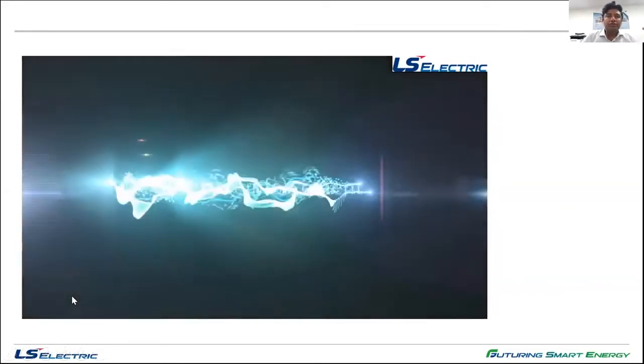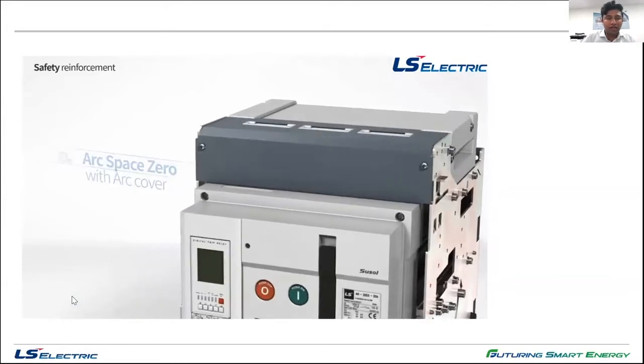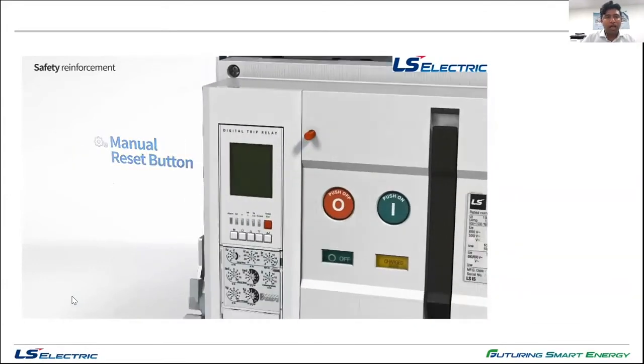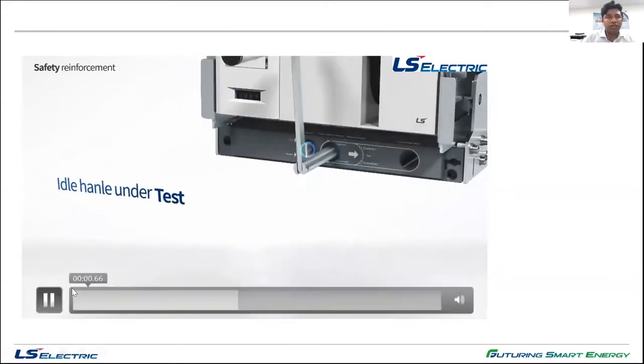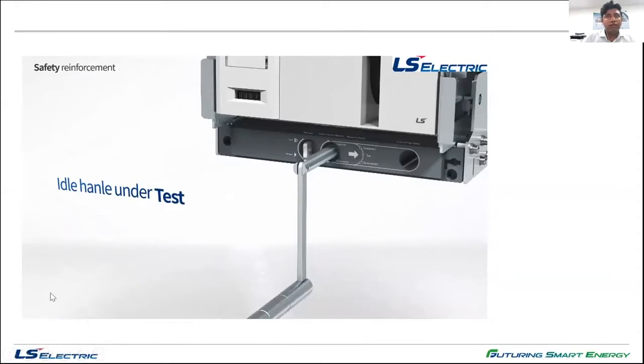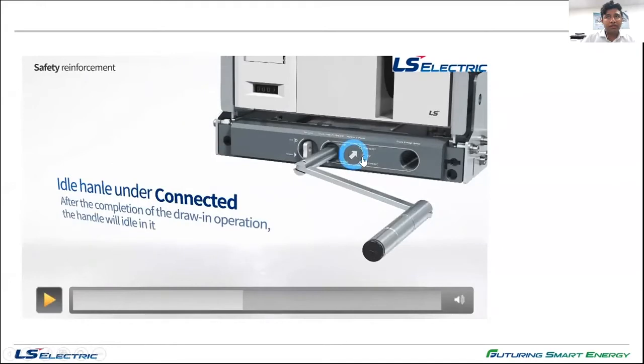And for the drawout ACBs, we are normally providing a shaft to withdraw the ACBs. Now, if an unskilled worker wants to remove the ACB from a live position, he has to first make sure that the button is in off condition. Without the off condition, the crankshaft will not be going into the cradle. So we make sure that the safety measures are intact, then only they will be able to withdraw the ACB. And the physical conditions like connected, test position, and disconnected positions are marked physically in front of the cradle.